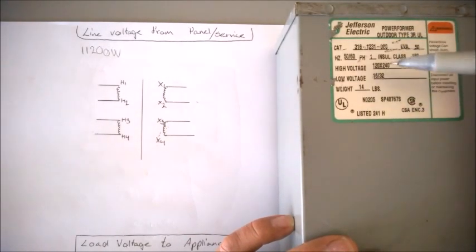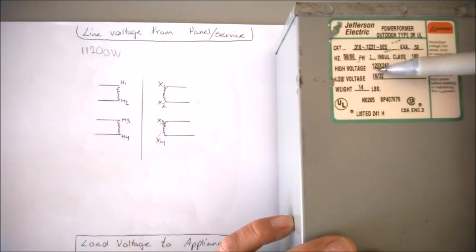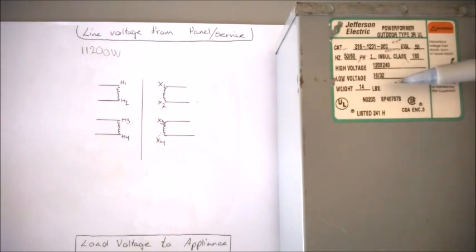Secondly down here is where you want to pay attention to—this is a 16/32, so that's what we're boosting on a 120 or 240 circuit. If we have two phases across our incoming voltage, you're going to be able to either buck or boost with 16 or 32 on this one.